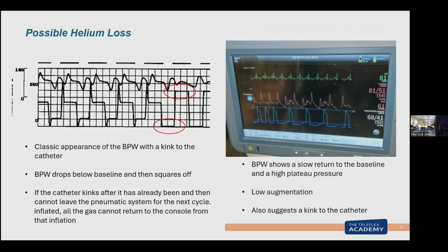So here's 1. Down below 0. Oh, we went to 1 to 2. It finally got back. So I know I'm dealing with a kink here because I can't get back because of the kink. Look at that. High plateau. His augmentation is only 61. Low augmentation because it's not getting very much volume to the balloon to inflate it. But when I went 1 to 2, at least I could see more augmentation. Not really here, because I can get the helium in and out a little better. Now I have to go after relieving the kink. I'm trying to figure out where the kink is. And I end up having to try and drop the volume to get past the kink.